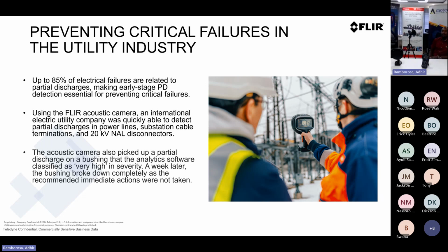We can look at the partial discharge. Up to 85% of the electrical failures are related to partial discharge, making early stage partial discharge detection very important in preventing the critical failures. So using this FLIR acoustic camera, which is part of the case studies that our colleagues from FLIR have done with an international electric utility company, they were able to detect the partial discharges in power lines, substations, cable terminations, and 20 kV disconnectors.